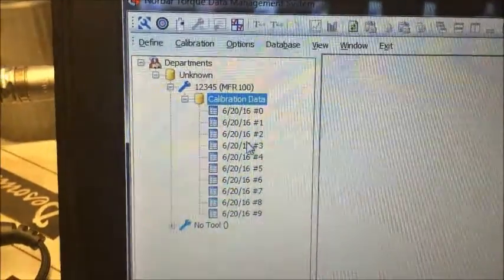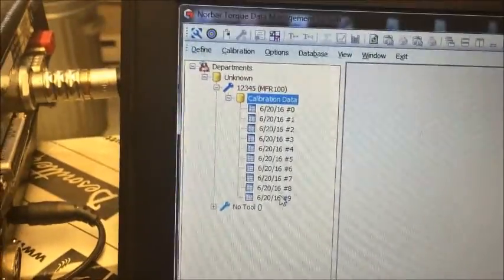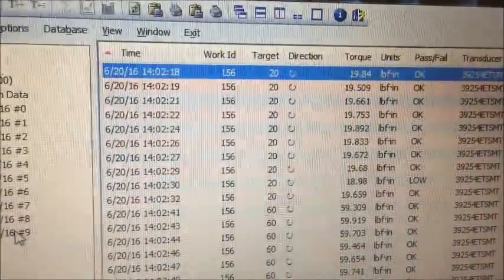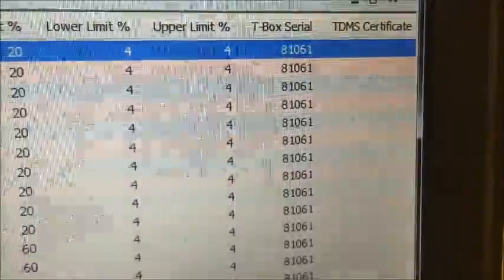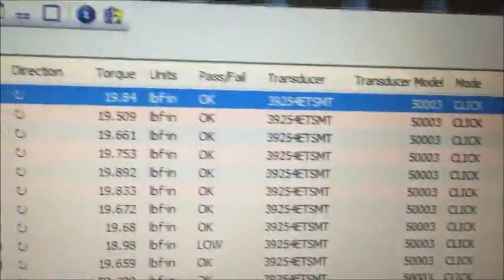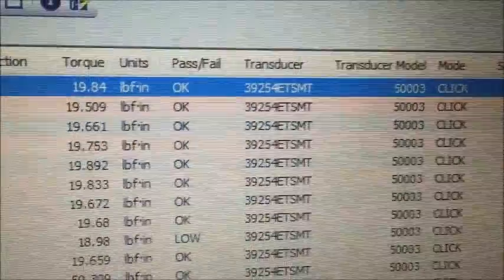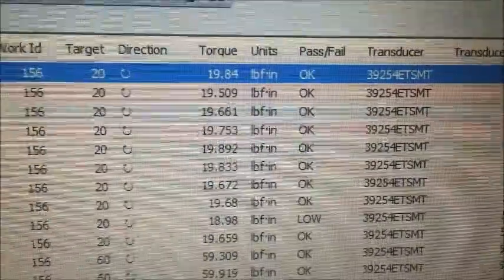We double click on it, it opens up, we see our calibration data. Here's all the different times I've tested it. The last one I just did here, we can click. Here's all our data. 20%, 60 and 100%, 10 different readings. Time and date stamps. It tells us the serial number of the tester we used, the target set points, the tolerances, the transducer model number that we programmed in earlier, and all of our torque values right here.